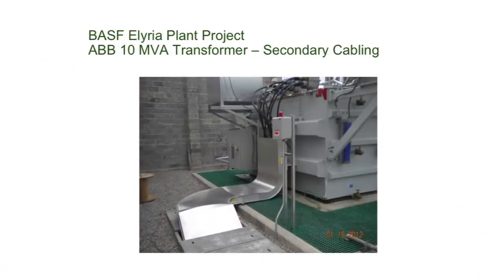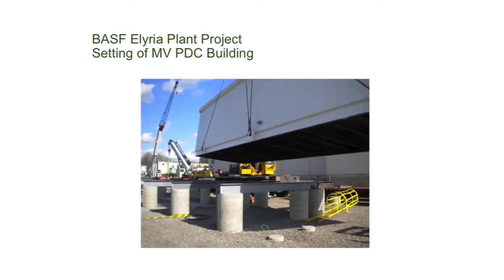It's just a close-up picture of the secondaries showing the Pfister connections and then the cables going underground, running over to the PDC building and the medium voltage switchgear. Setting of the PDC building. Building was fabricated in Houston, and building showed up pre-installed with the medium voltage switchgear, the micro-SCADA system, all pre-wired, all tested at the building manufacturer site before we split the building. The building was shipped in 2 sections.